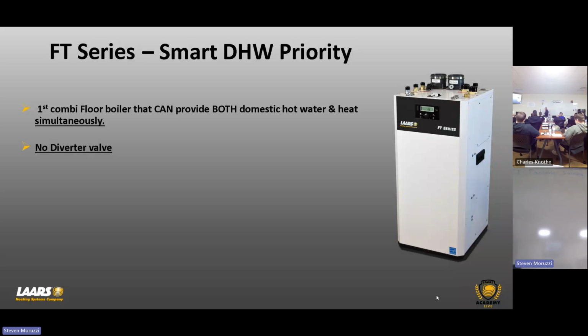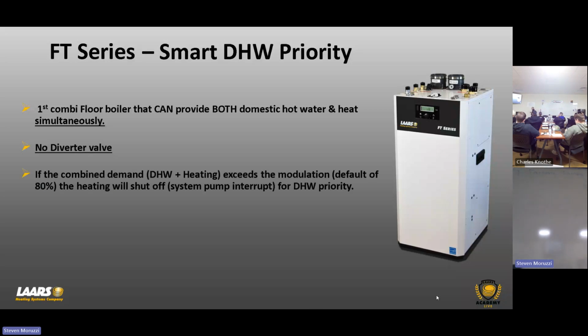By doing it this way with no diverter valve, we can provide both heat and hot water. How does it work? It works off modulation. So hypothetically, I've got a zone of heat or 2 zones of heat running, call it 80,000 BTUs. I got a 199,000 BTU boiler. So I still have ample BTUs for the indirect tank, and so we can provide both. So how it works is on my modulation. If the boiler modulates to 80% of modulation, we want to control that zone pump system or that zone valves.